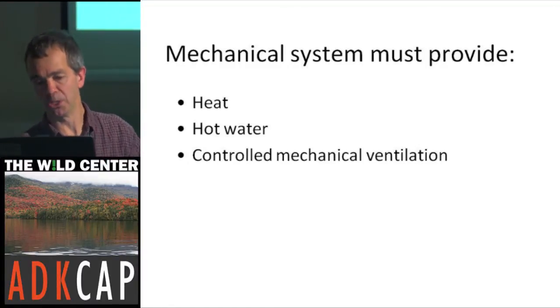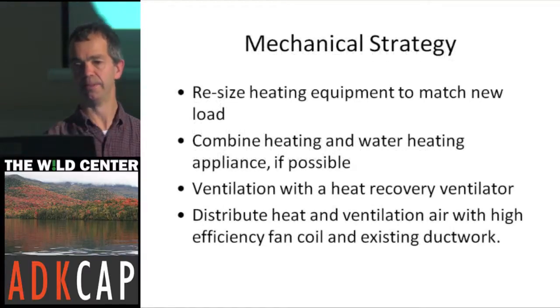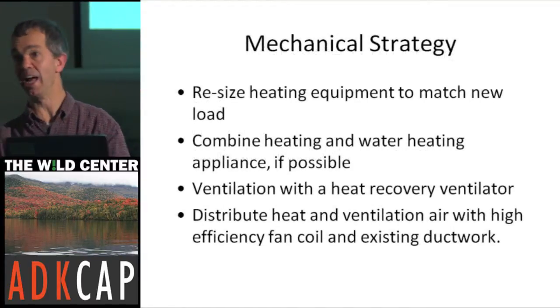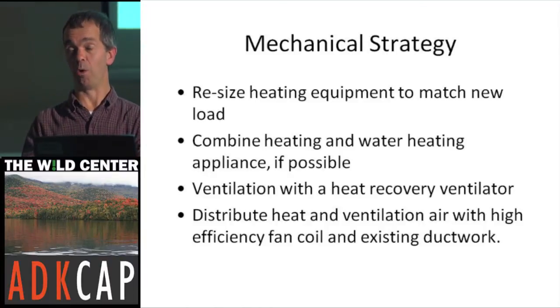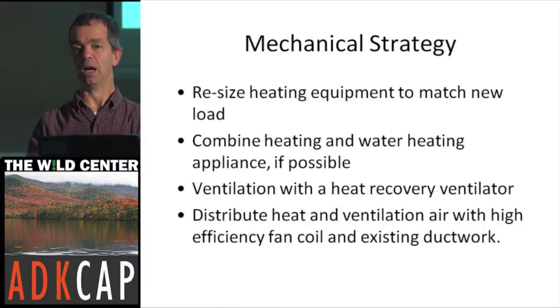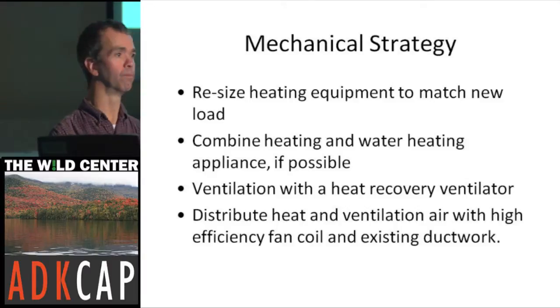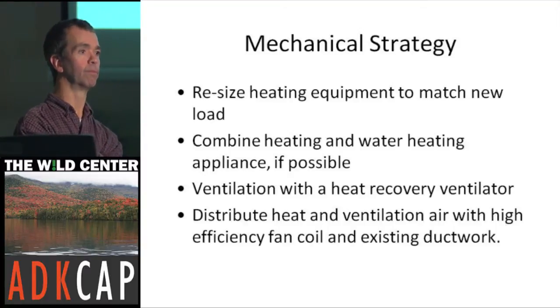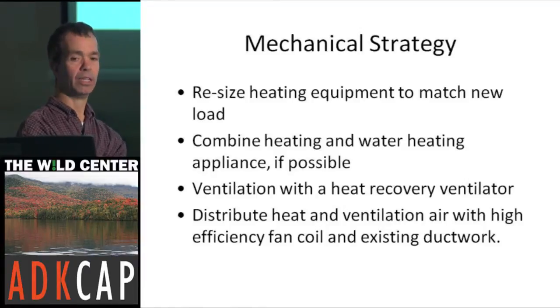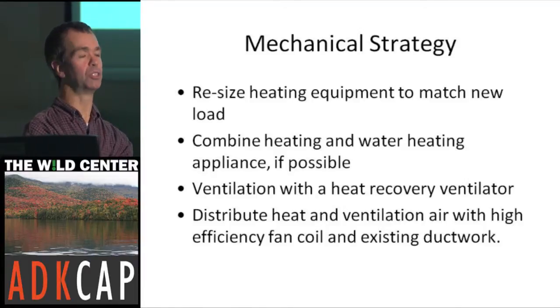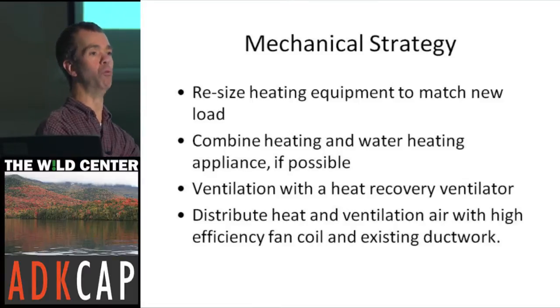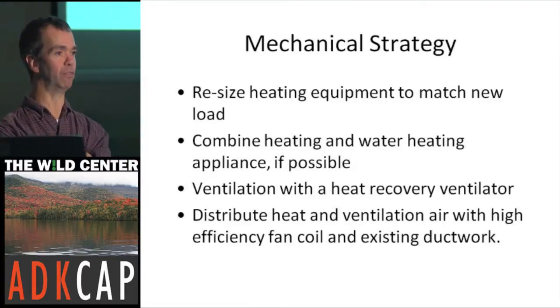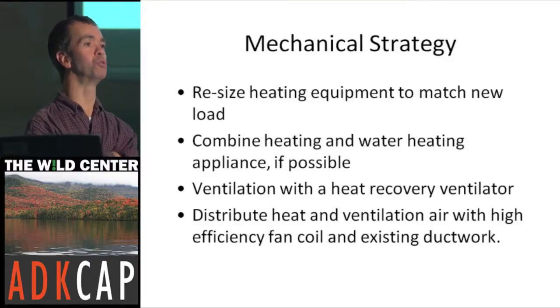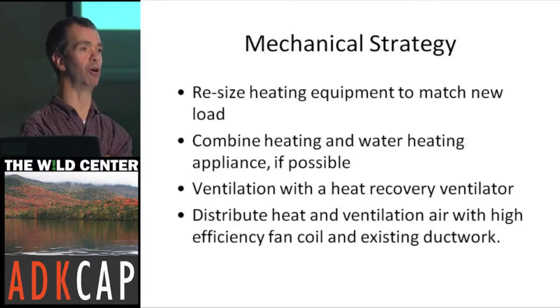But since they had basements and furnaces, we married into that, resized the heating equipment, and concluded that was the best solution, using a tankless hot water heater. So 200,000 BTU down to about 40, less, because of the insulation. That's the benefit, that's basically your hurrah moment when you've built or optimized the envelope. Now you can take advantage of much, much smaller equipment.